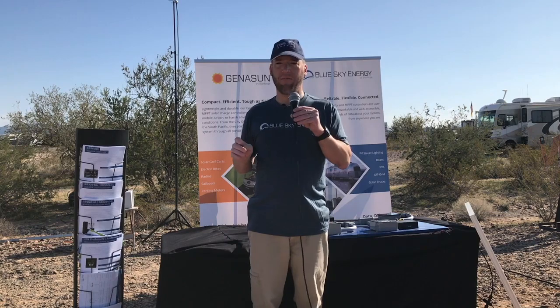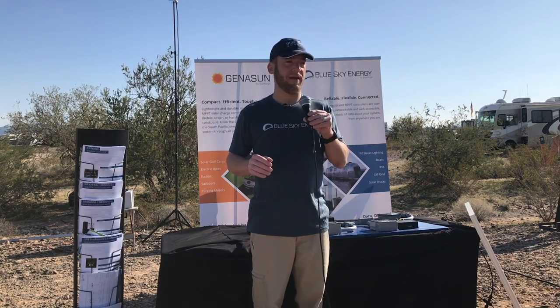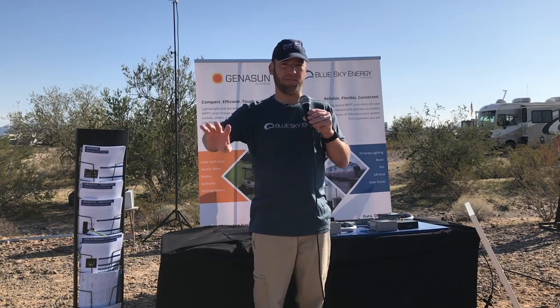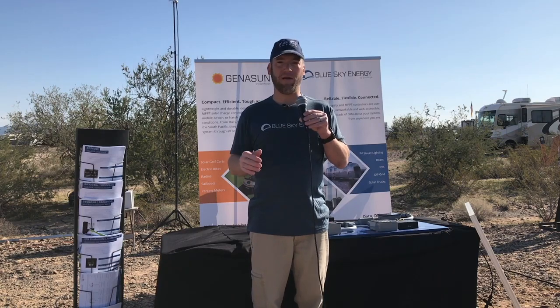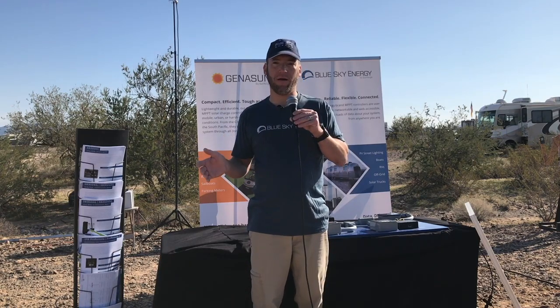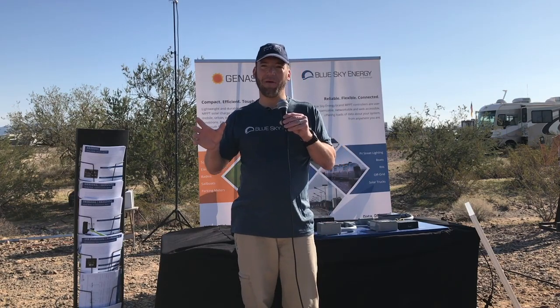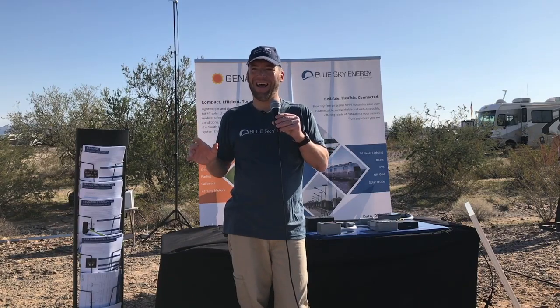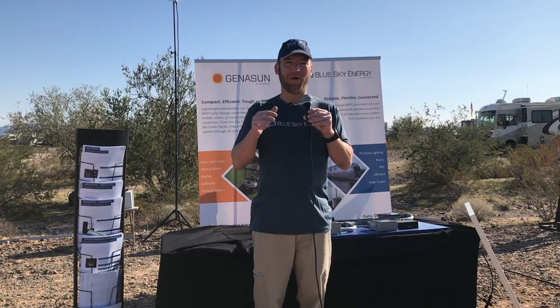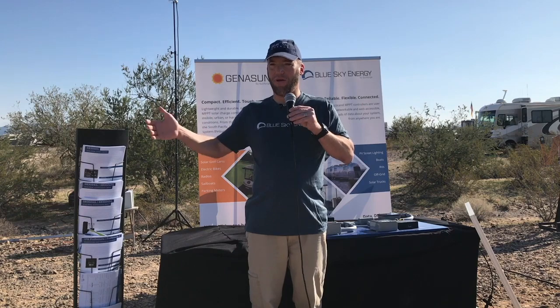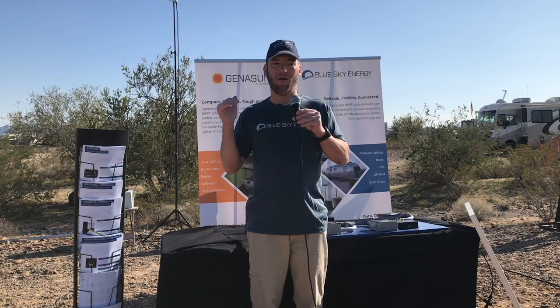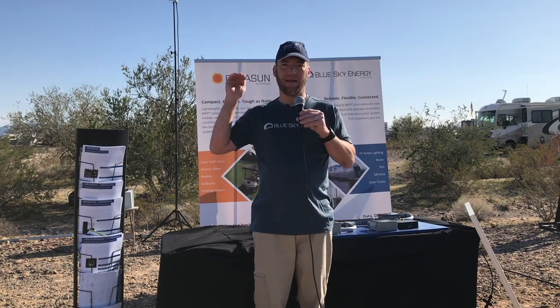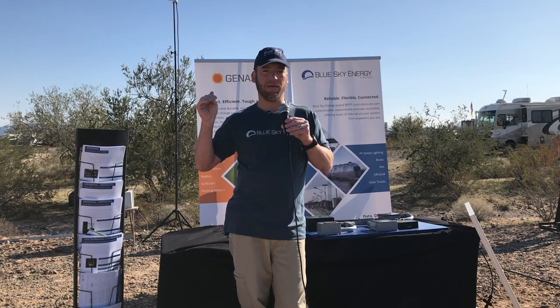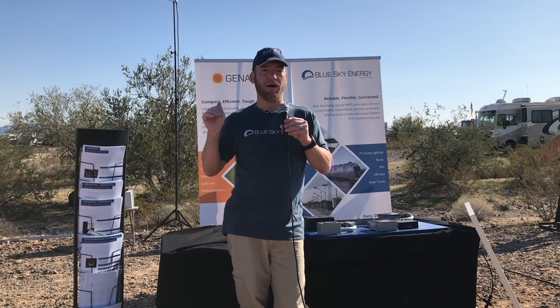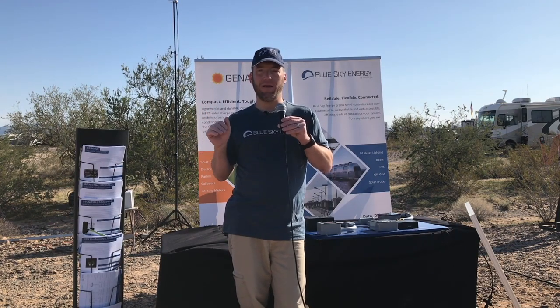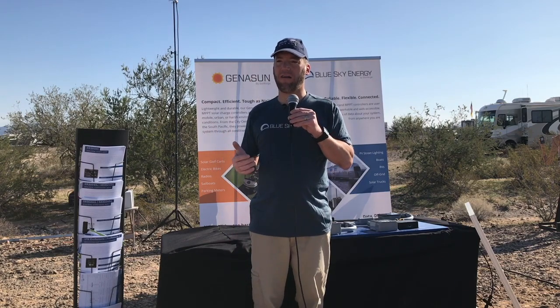The preferred time varies among manufacturers. I've had some say 12 minutes is plenty, and others, like Battleborn, say 1 hour per battery. I think that's a little excessive, but that's what they want, that's what they get. I can almost live with 1 hour per battery bank, but the longer you hold a lithium battery at that charge voltage, or in the lithium world they call it the balancing voltage instead of the absorption voltage, the harder it is on the cells.